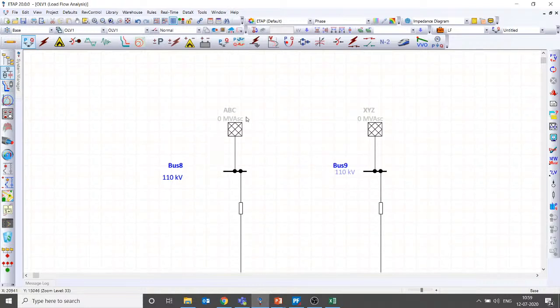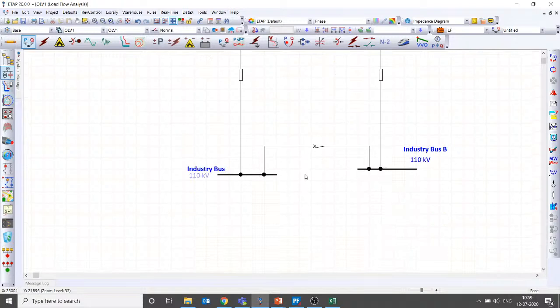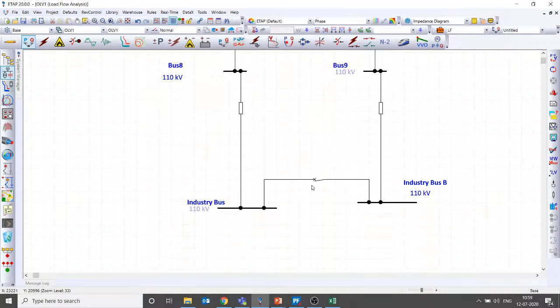But if this is coming from some other place, then designing the system is a bit difficult. You should not parallel two different substations at your industry bus. If it is not coming from two different substations, if it is the same station and you have a double circuit line, that's fine. You can parallel it. I believe that is clear, Vishal.